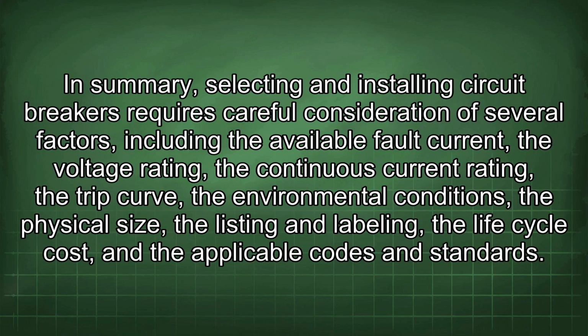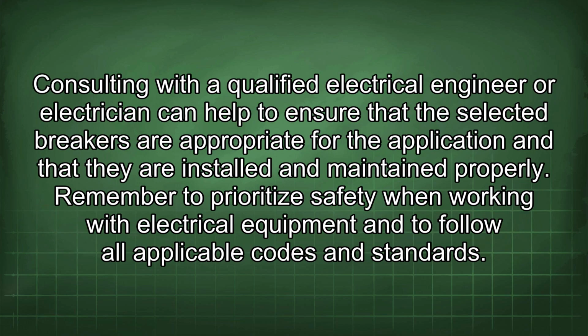In summary, selecting and installing circuit breakers requires careful consideration of several factors, including the available fault current, the voltage rating, the continuous current rating, the trip curve, the environmental conditions, the physical size, the listing and labeling, the life cycle cost, and the applicable codes and standards. Consulting with a qualified electrical engineer or electrician can help to ensure that the selected breakers are appropriate for the application and that they are installed and maintained properly. Remember to prioritize safety when working with electrical equipment and to follow all applicable codes and standards.